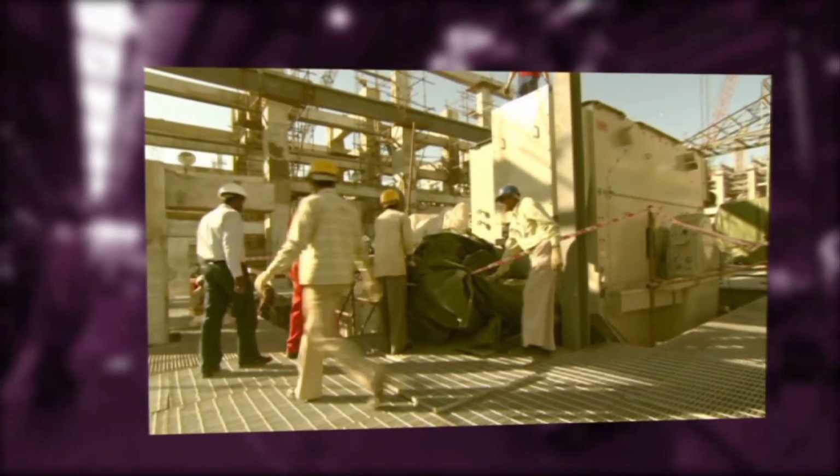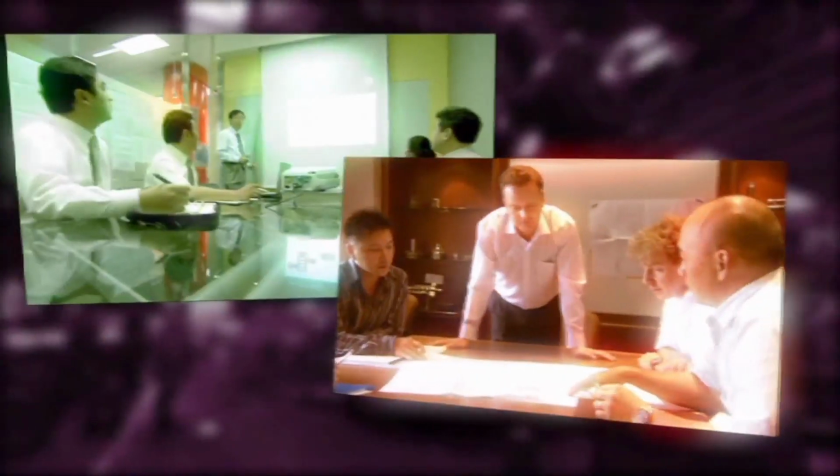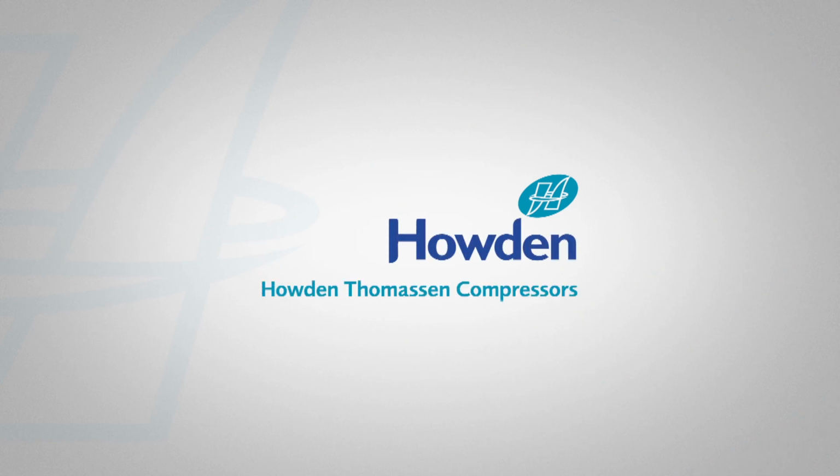So far, we have fitted 200 free-floating pistons to new-built and re-rated compressors. What's more, as at June 2010, the first free-floating piston compressor has clocked up 80,000 hours on its original rider rings. Putting the principle into practice.